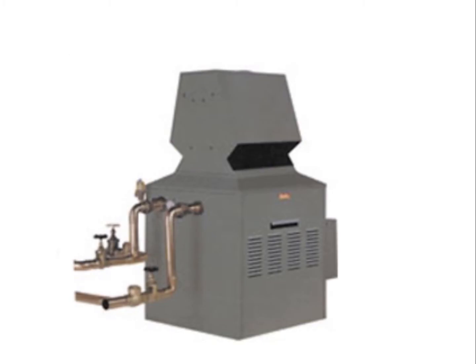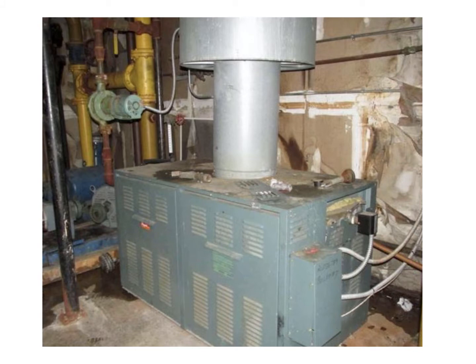Domestic hot water heating systems come in all different types, sizes, shapes, and configurations. Shown is a large commercial copper fin tube boiler that is typically tied to a storage tank, but not always necessarily. They do make one of these units that is fully modulating that does not require a storage tank. Domestic hot water heating can be done either directly with a copper fin tube boiler, or it may also be done indirectly with an indirect or a reverse indirect type of storage tank that utilizes a closed loop space heating boiler as its heat source.